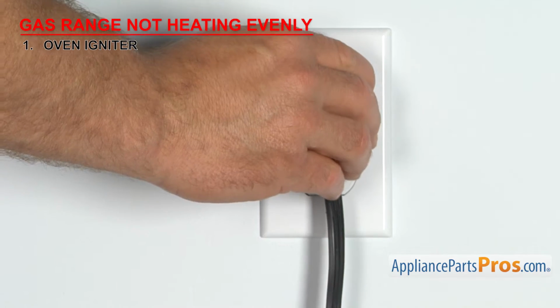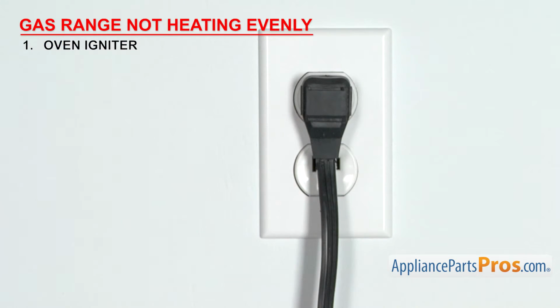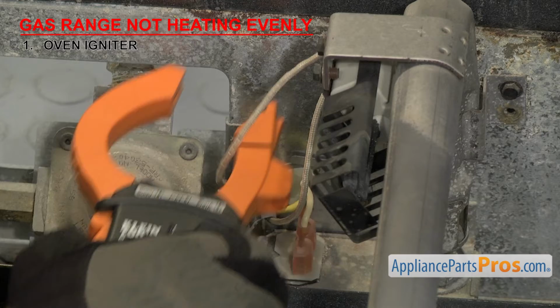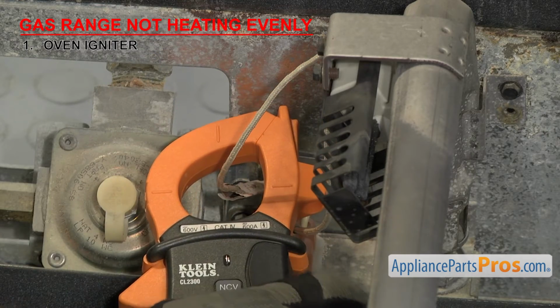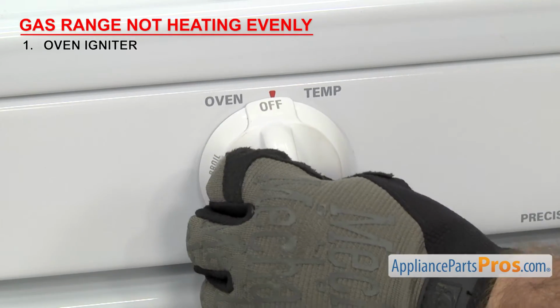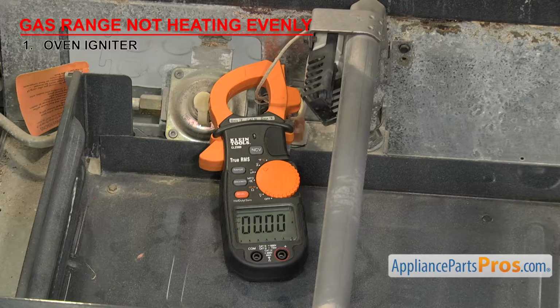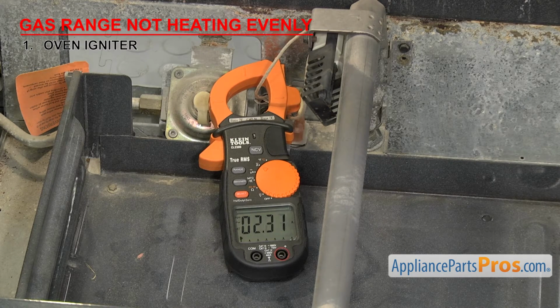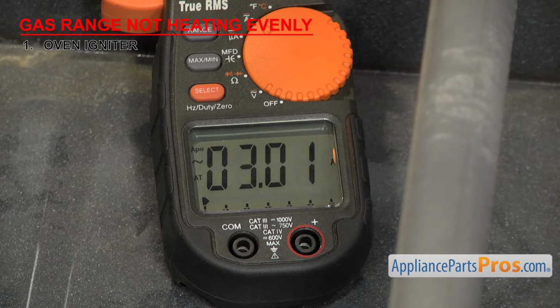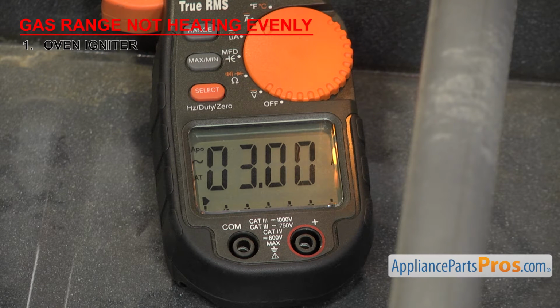So temporarily turn the power back on, but leave the gas off. Then clamp the amp meter around one of the wires from the igniter and turn the oven on. If the igniter isn't drawing enough amps, it'll have to be replaced. Usually the igniter will not read all the way up to 3.3 amps due to age, and they can read even less and still open the safety valve. But anything less than 3.0 for the square igniters or 2.2 for the round ones is questionable and may not open the safety valve in the required time.